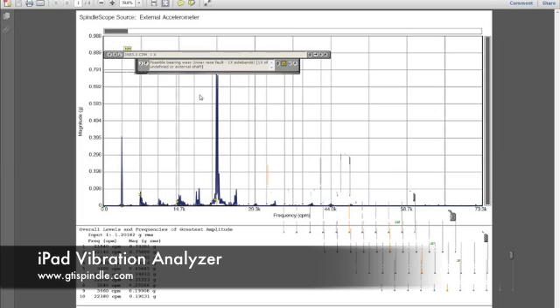Here's the running speed here, the high peaks at very many times the running speed. And in this case, again, Interpreter is correct.